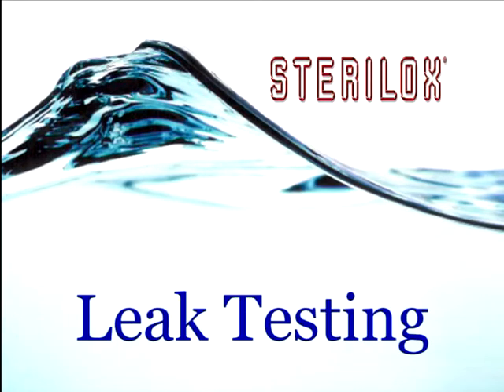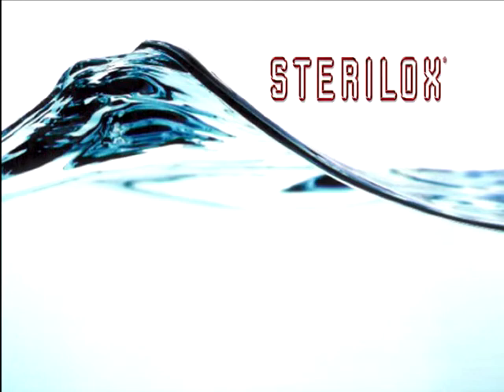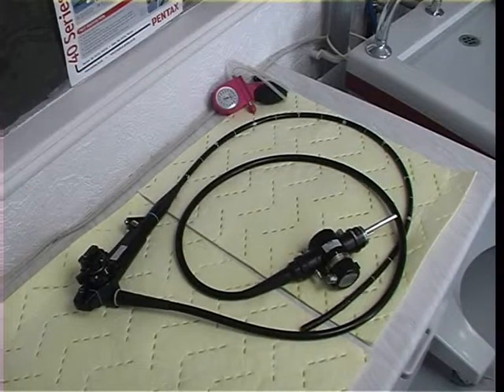Leak testing. Leak testing must be carried out according to endoscope manufacturer instruction, the BSG and MDA guidelines, and your unit standard, and before each patient use of the endoscope. In theory, leak testing allows air pressure to be applied around the channels via the internal space of the sheath covering of the endoscope. This procedure gives early detection of a leaking scope. Early detection can substantially reduce the cost of any repair.